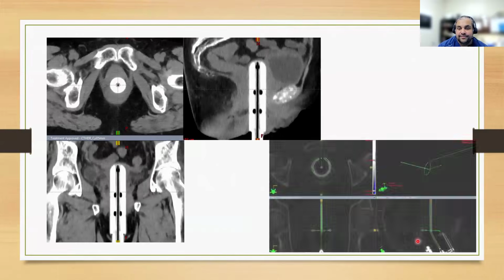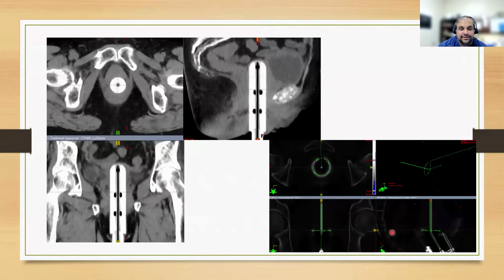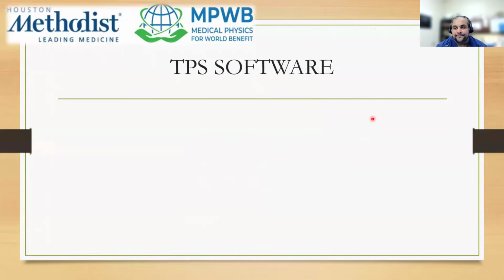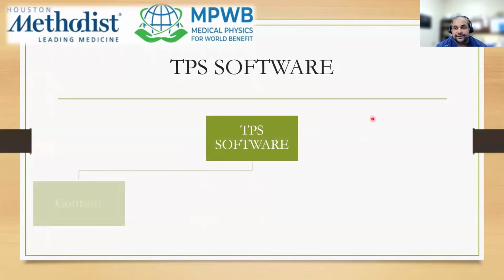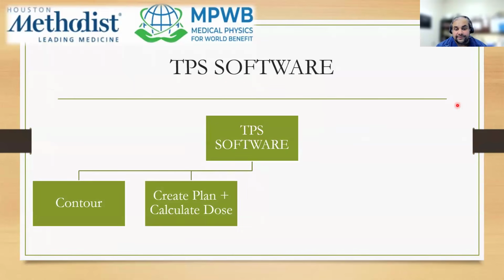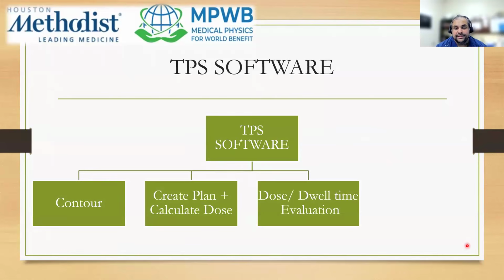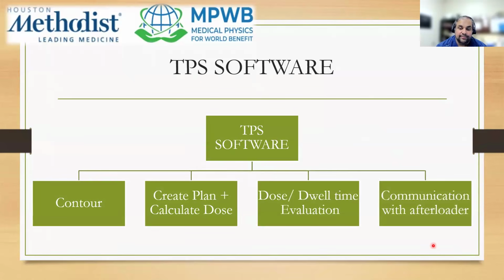So you can see over here, typically, you import the images, and you can do your applicator reconstruction, and then based on the treatment plan, import the plan, export the plan to your console, and then just run a test plan. For your software, you can test your contours, create a plan, calculate the dose, and evaluate your dose as per what you expect. Does it match? And then we have to test the communication with the afterloader.